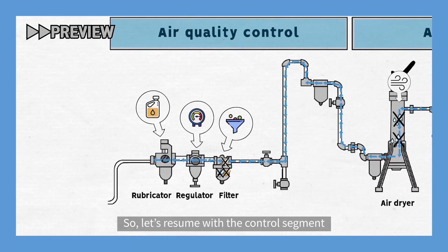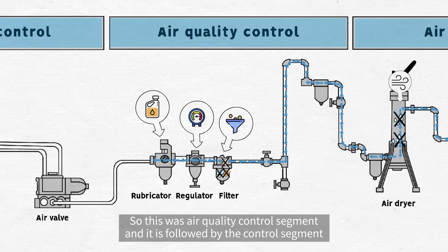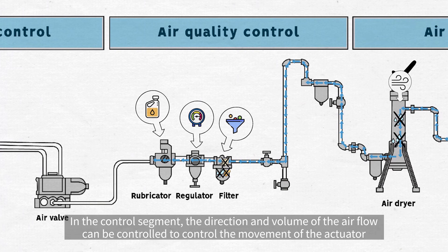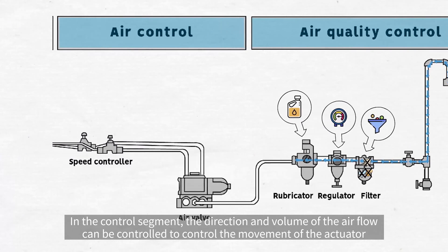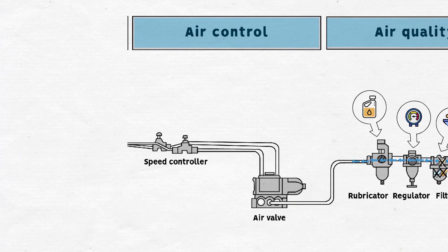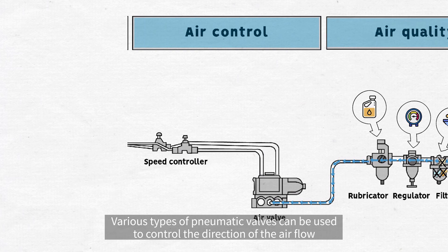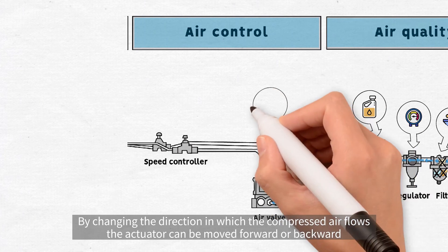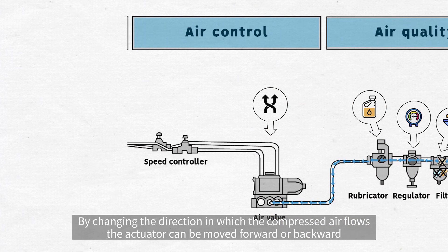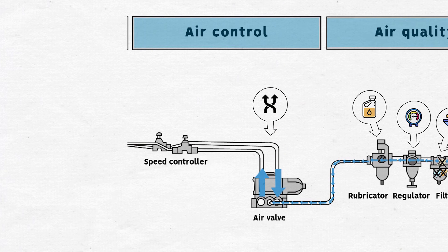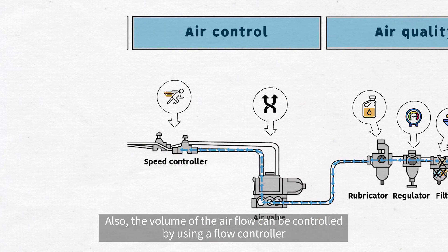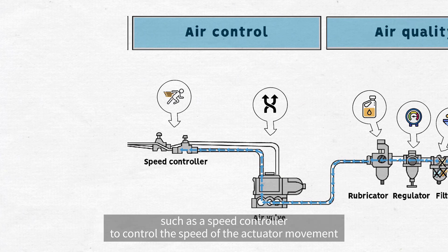So let's resume with the control segment. This was the air quality control segment, and it is followed by the control segment. In the control segment, the direction and volume of the airflow can be controlled to control the movement of the actuator. Various types of pneumatic valves can be used to control the direction of the airflow. By changing the direction in which the compressed air flows, the actuator can be moved forward or backward. Also, the volume of the airflow can be controlled by using a flow controller, such as a speed controller, to control the speed of the actuator movement.